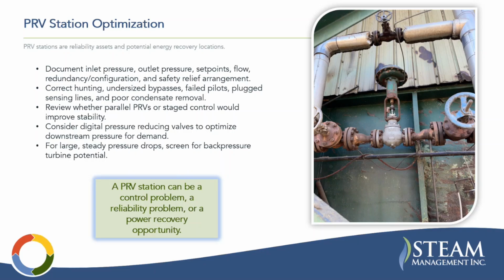That is replacing a PRV with a back pressure turbine. So you're generating steam at a high pressure, and you're sending it through a PRV. The exhaust of the turbine is coming out at still some pressure, 50 pounds, 10 pounds, whatever it is, and then that's feeding your 50 pound, 10 pound, whatever it is system that you have instead of having a PRV. So that's a really good scope if the conditions are conducive.